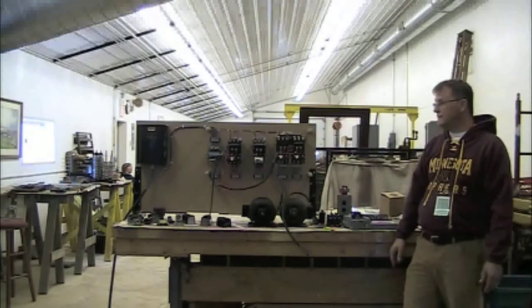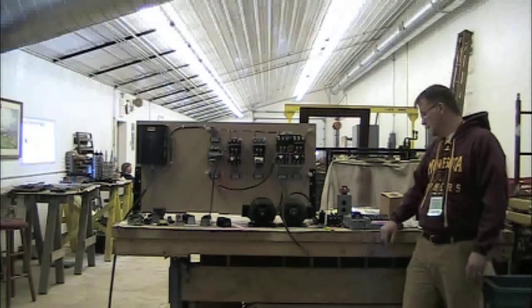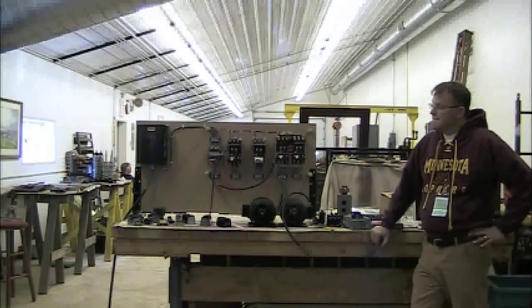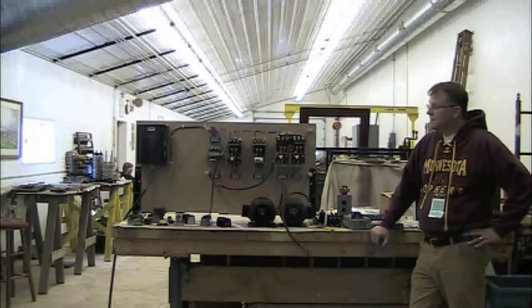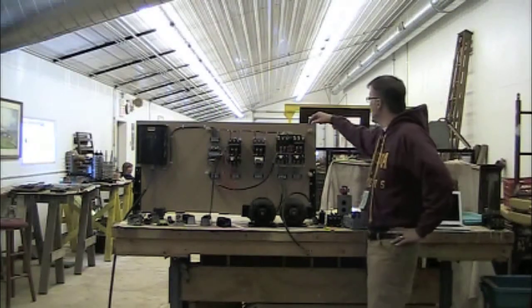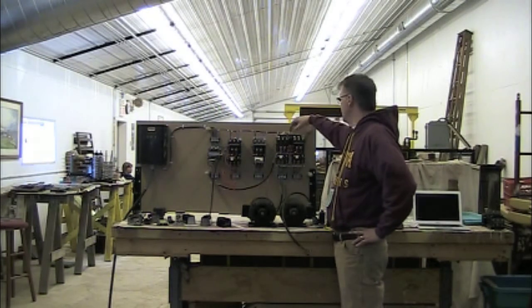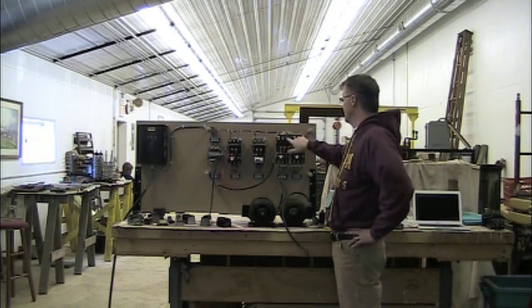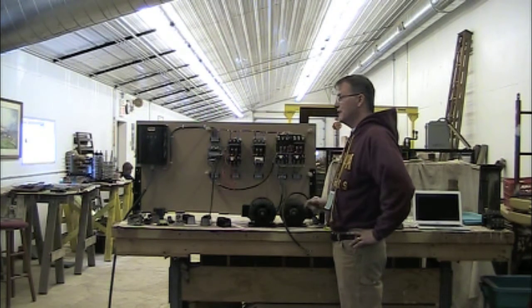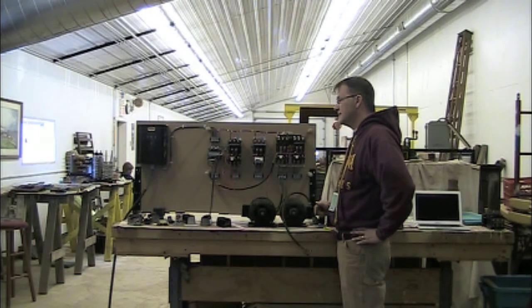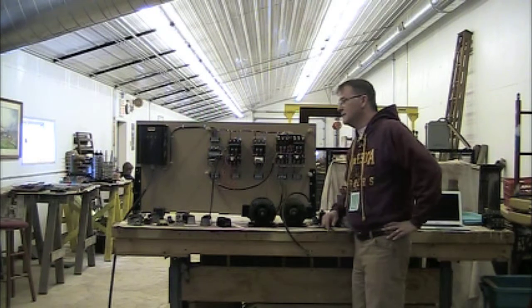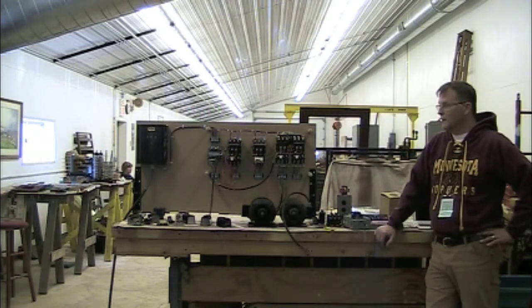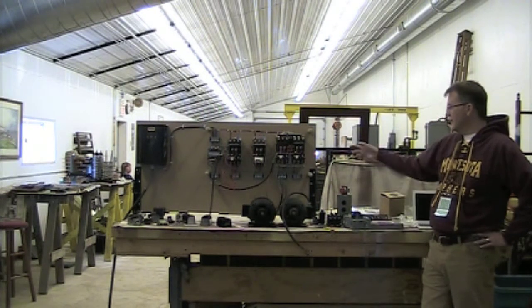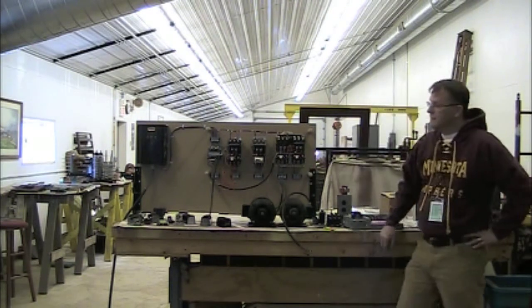So if you found a 2-winding 2-speed starter and you wanted to use it for reversing, all you have to do is twist the... You could just strip these off the back, off the top, and interconnect them with 3 wires. Exactly. Just so that it reverses. Right, and then you just have the same rating heaters in both of yours. Yeah, you'd have the same, and you just need to have the right set of auxiliary contacts, just logic-wise. I mean, I think you'd end up with the same thing for it.